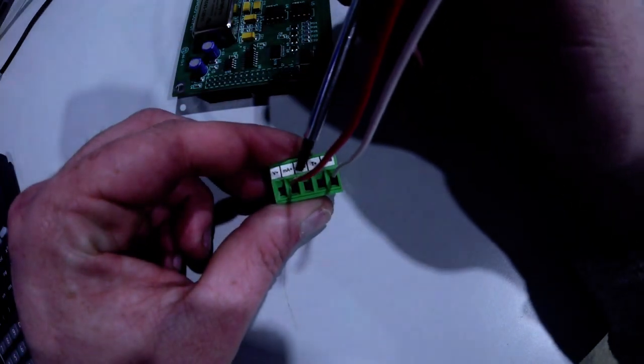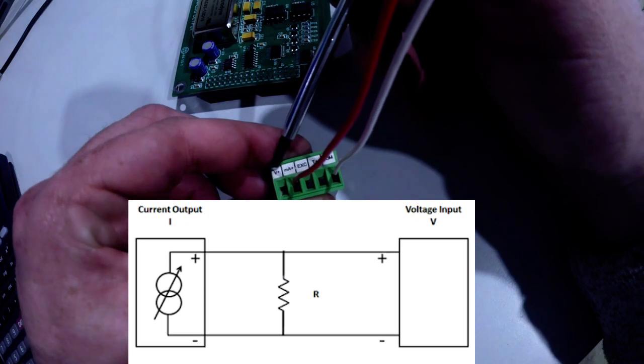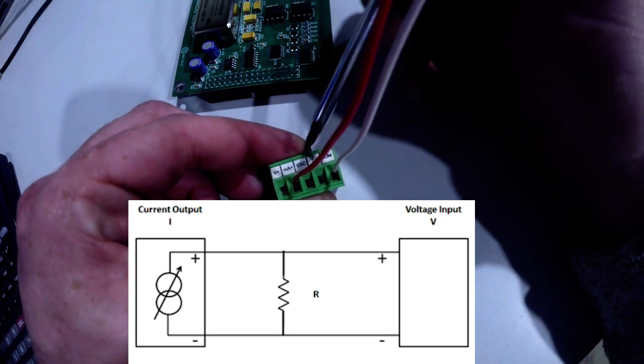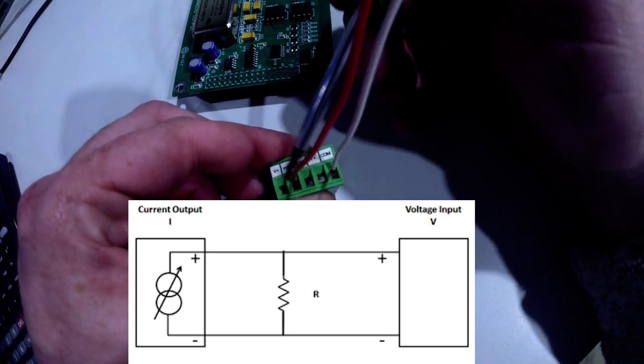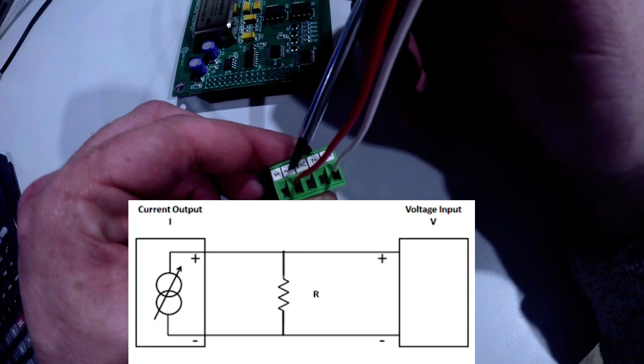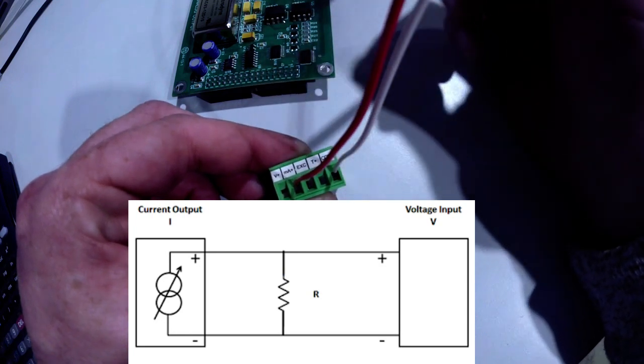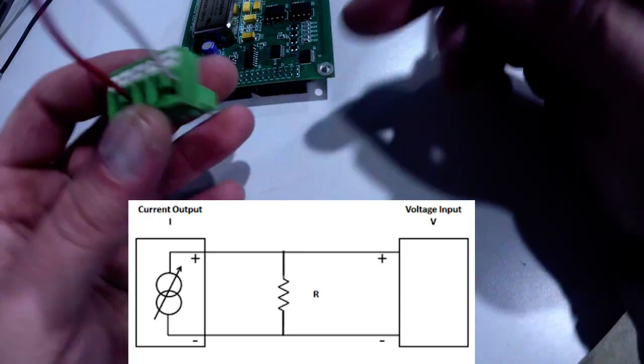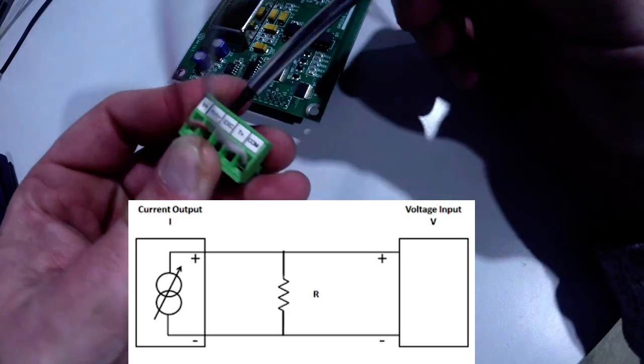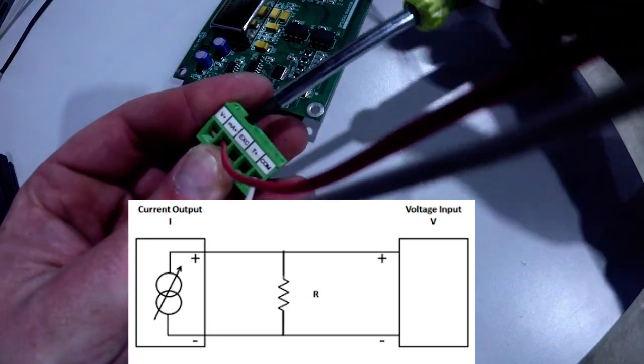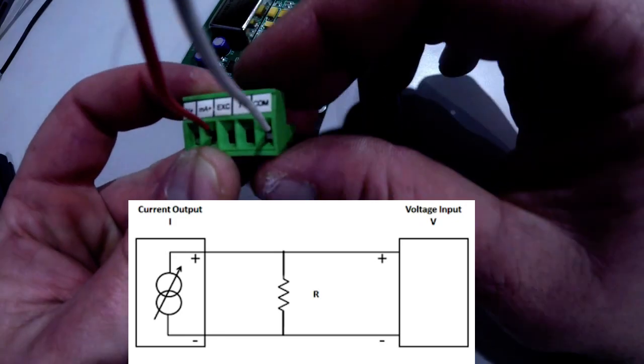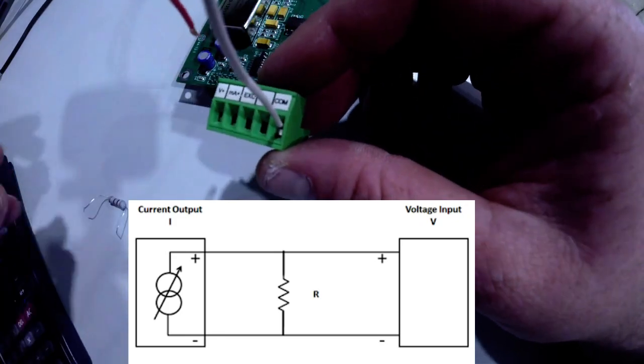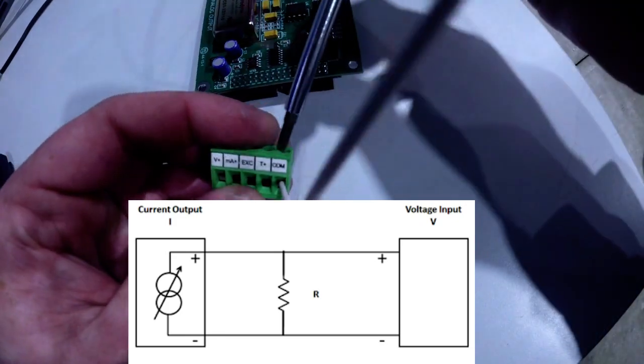So we could place a 500 ohm resistor in between our V plus and common and move this red wire to V plus. That's our I plus coming off our output card, and we can change this over to voltage output instead of a current output for this two-wire setup. So what I'm going to do now is disconnect our wires.